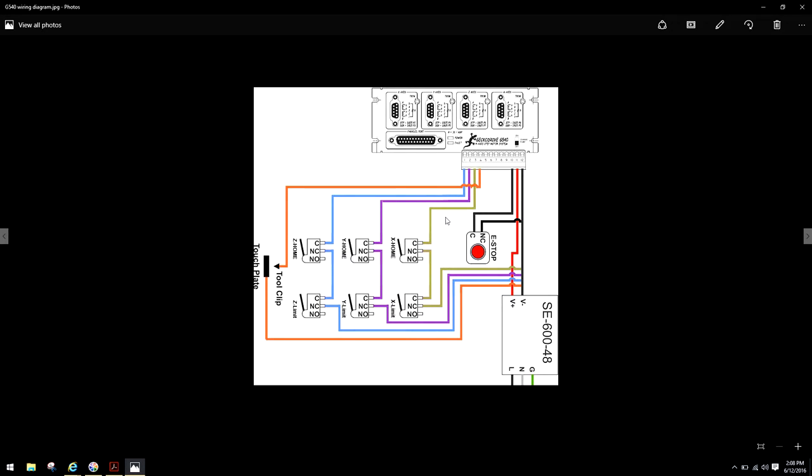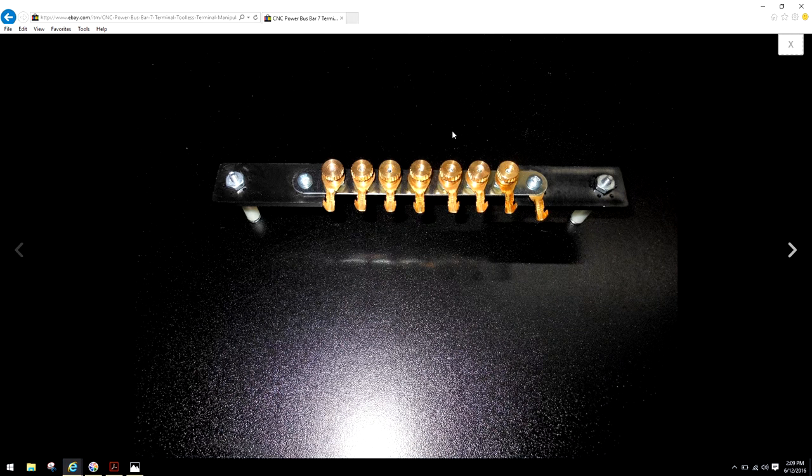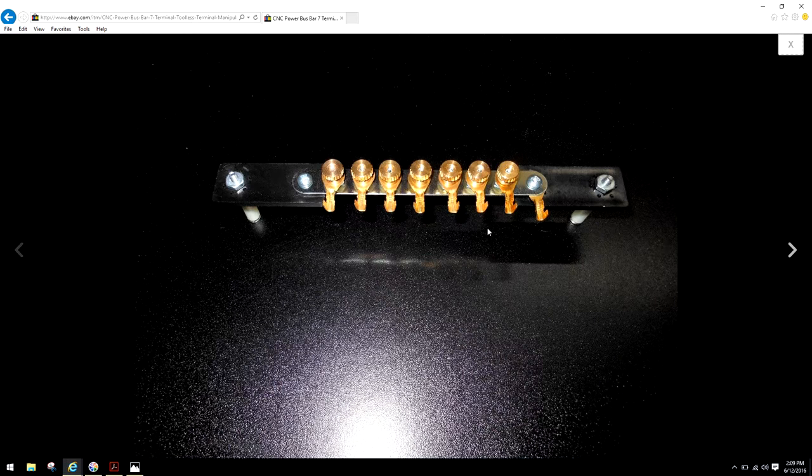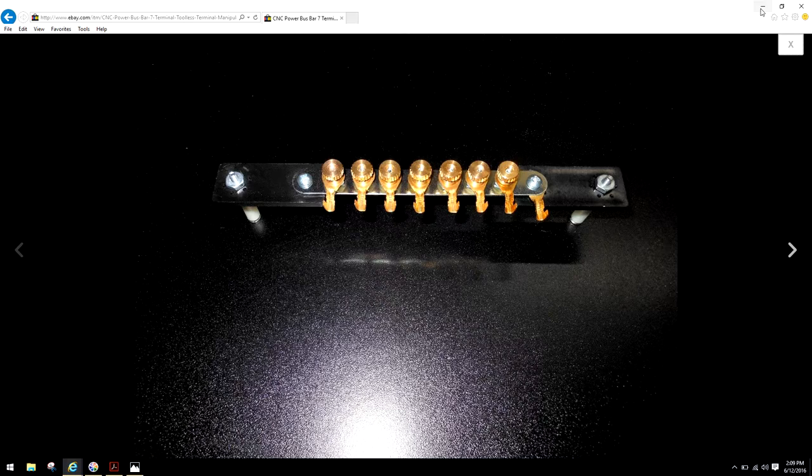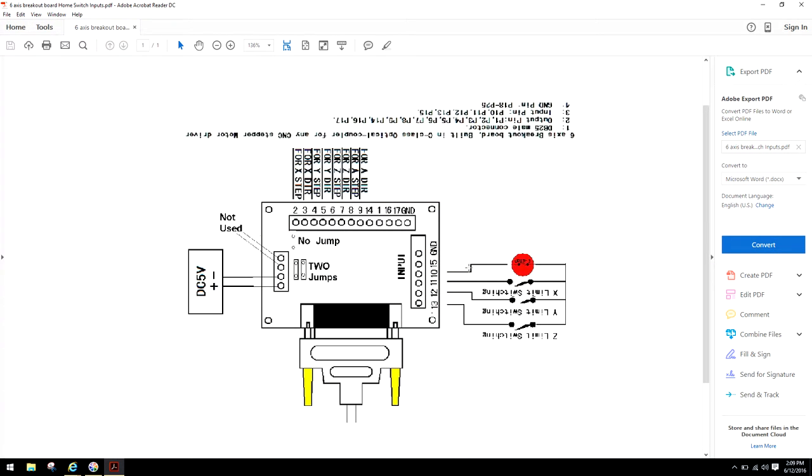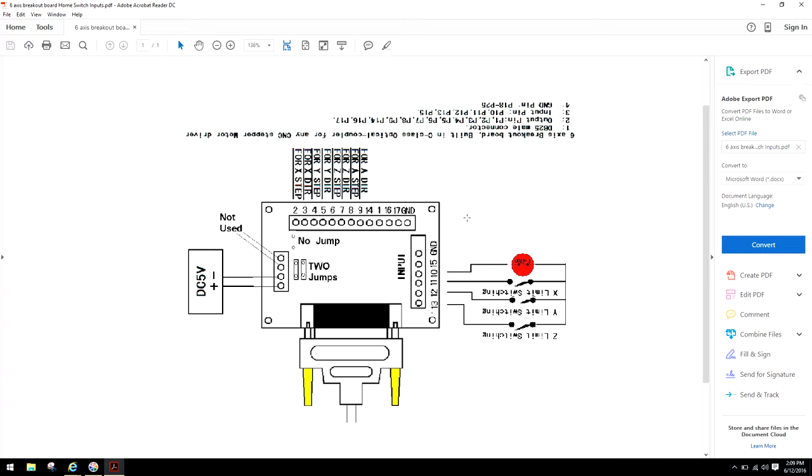Rather than having all these switches, I've seen it before, they'll have all the home switches wired into one terminal. If one of these switches goes out guys, you're going through them. You're going to check all four of them to see if they're working? That's ridiculous. You're much more efficient to spend the money from the beginning and do it right, and actually distribute the signal properly to where each connection goes to one switch. And then you can come back over here and look back and go, I found out which switch was bad. It took me two seconds because I knew all my other switches were up and working.